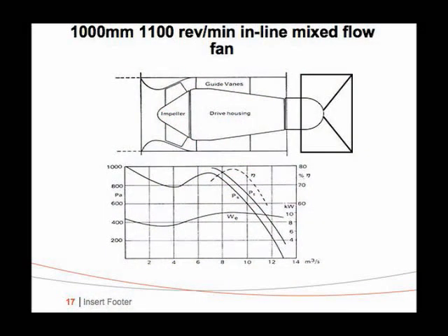This is the way it's done at present in this fan. And this is very high friction loss because the air doesn't see the entire cross-sectional area. It only sees the annulus. So what we need to do is to borrow from Pratt and Whitney on jet engine discharge. You need to do this to get very low friction loss on the discharge because we need to look at system efficiency for the fan. And if I can leave one message with you, fan systems need to look at 10,000 CFM per kilowatt.